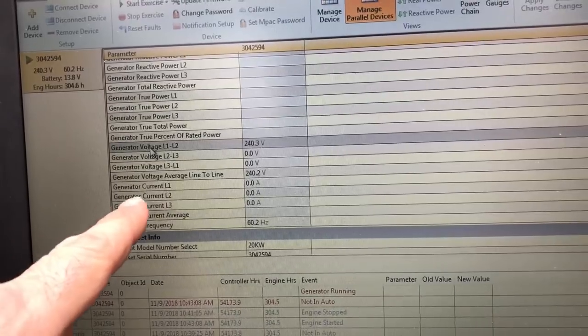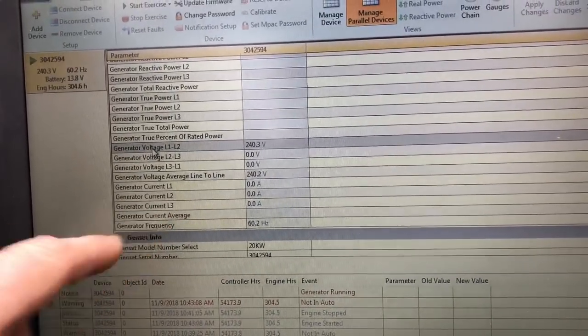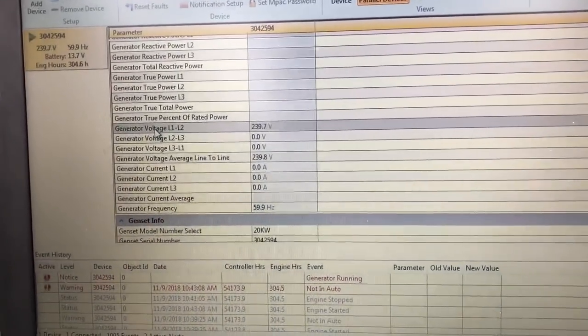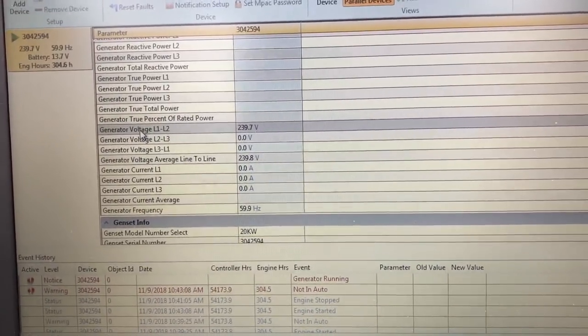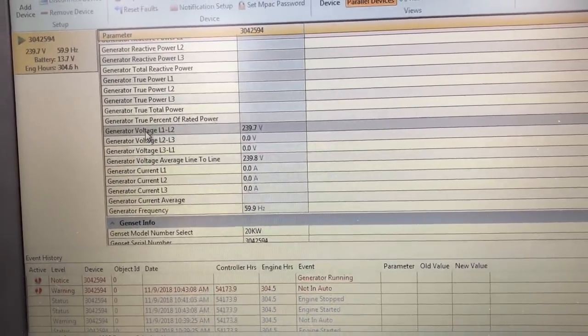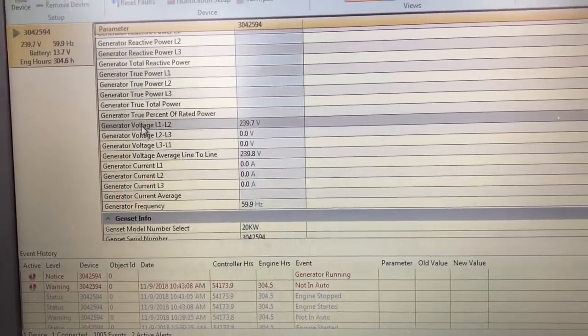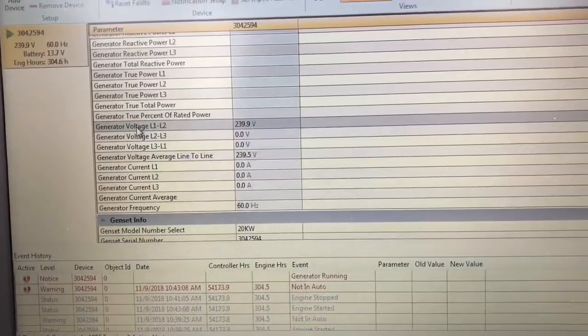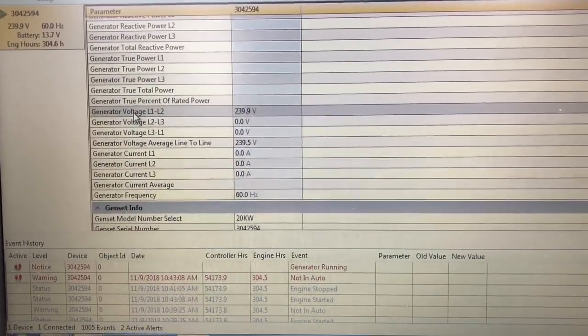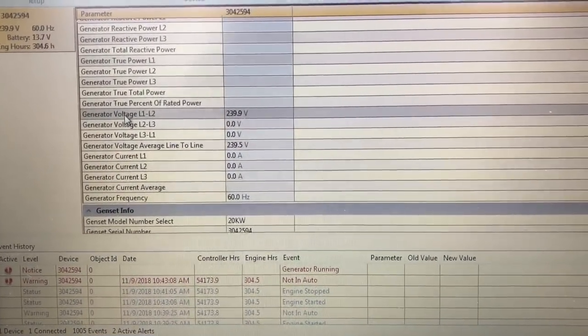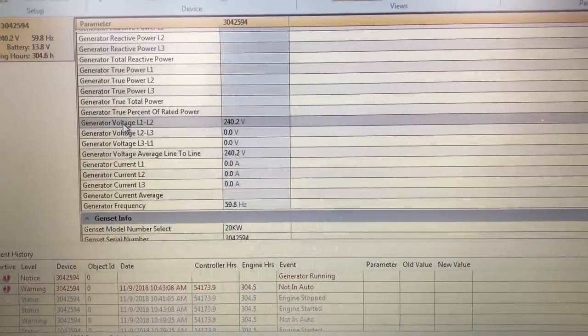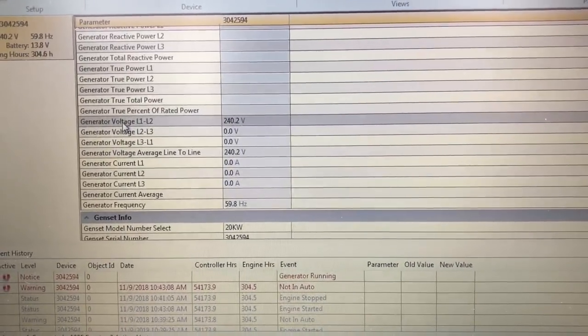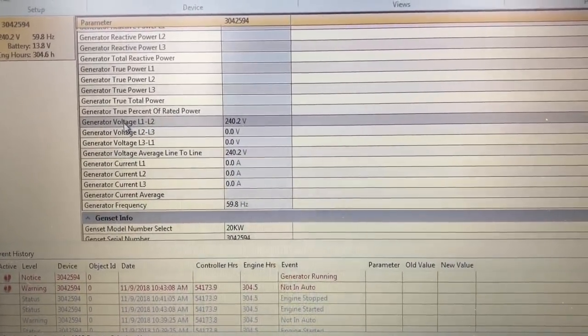And then I don't have any current at all right now. I'm not powering the house, I have zero current on it. My frequency is almost 60 hertz, and that's pretty much how the generator controls and operates its speed bias. Looking at the key, 60 hertz at all times.